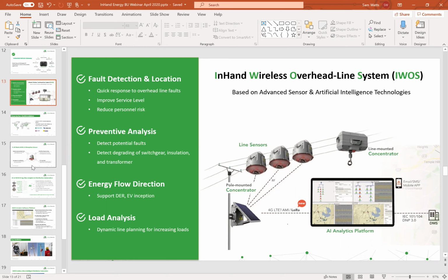The sensors work 24/7 at 256 cycles a second, sampling and measuring the current amps, the E field, the harvesting voltage, the temperature of the line or conductor, as well as featuring a time clock and a GPS. There are 3 sensors, typically up to 9 from one base station, but typically we'll see 3, and those go on each phase—1 goes on each phase.